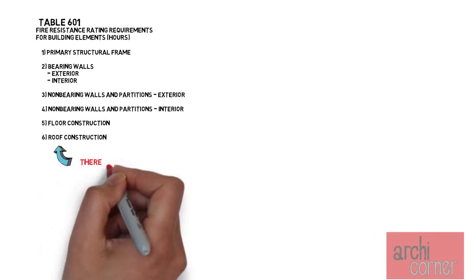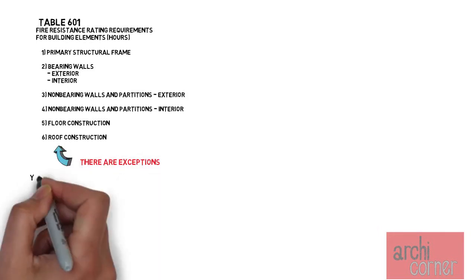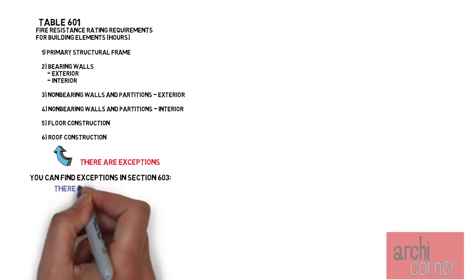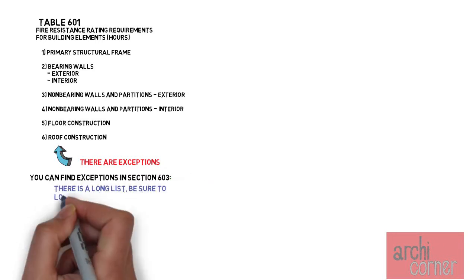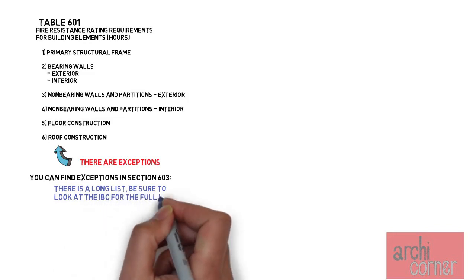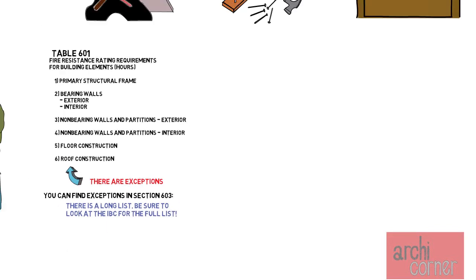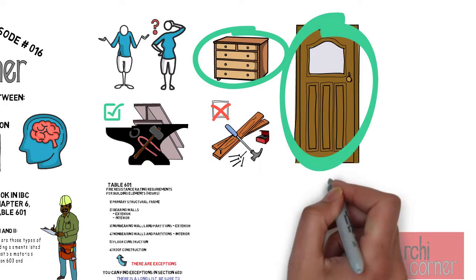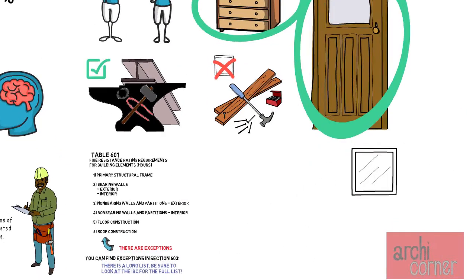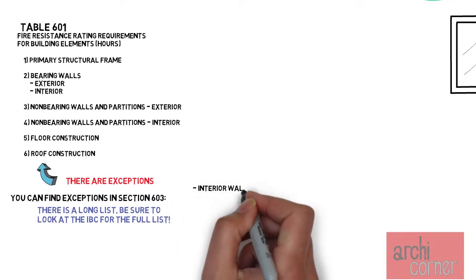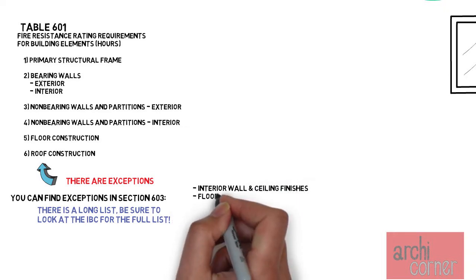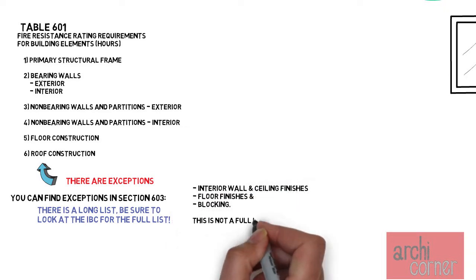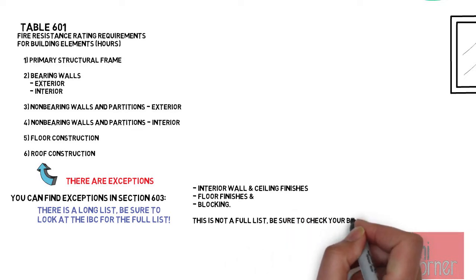Section 603 also has some exceptions for other items that may be combustible. It's a long list — currently there are about 26 different items that are exempted, some of which we've already talked about: items such as millwork, doors, door frames, window sashes and frames, interior wall and ceiling finishes, finish flooring, and blocking that can be used for handrails, millwork, or other items.